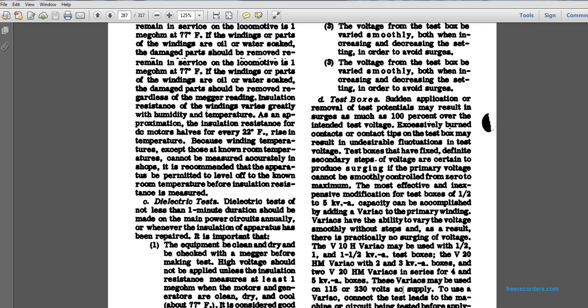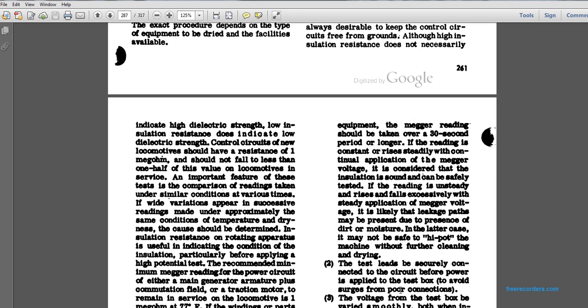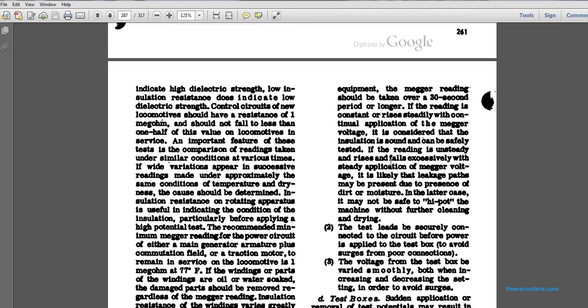In the case of diesel electric locomotives, the megger reading should be taken for 30 seconds or longer. If the reading is consistent and rises steadily with the continued application of the megger, it is considered that the insulation is sound and can safely be tested. If the reading is unsteady and rises and falls excessively with steady application of the megger voltage, a leakage path is likely present due to dirt and moisture. In such cases, it may not be safe to apply a high potential to the machine without further cleaning and drying.